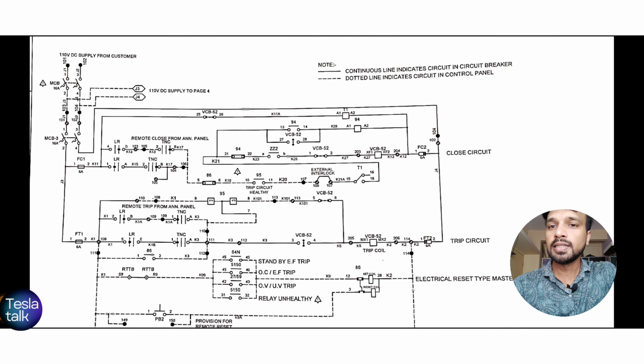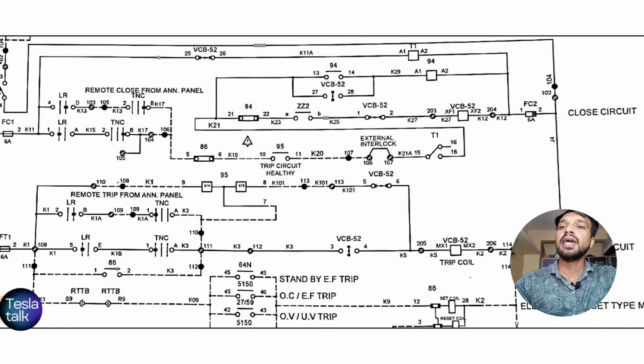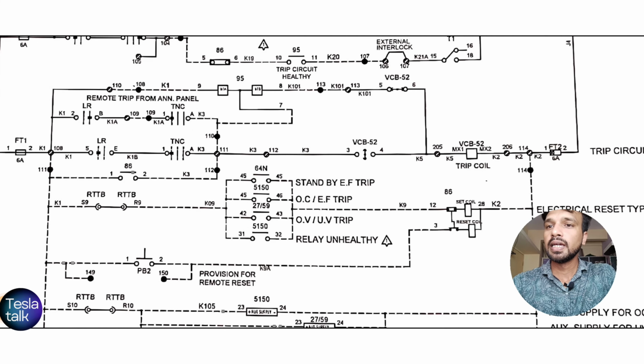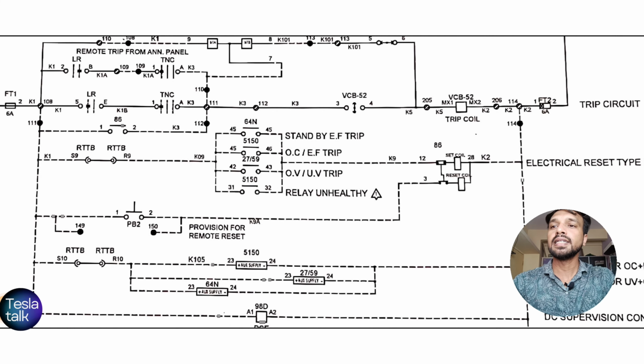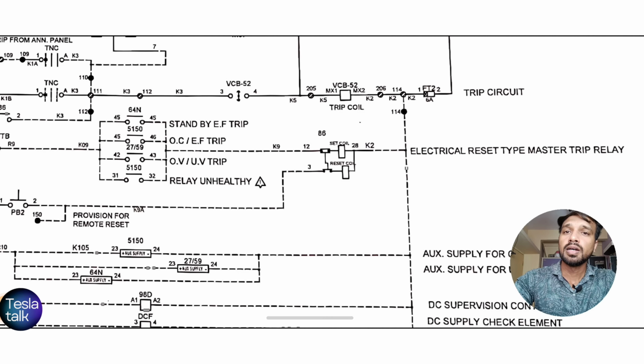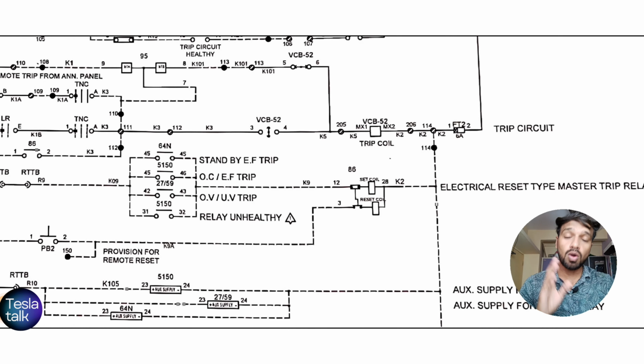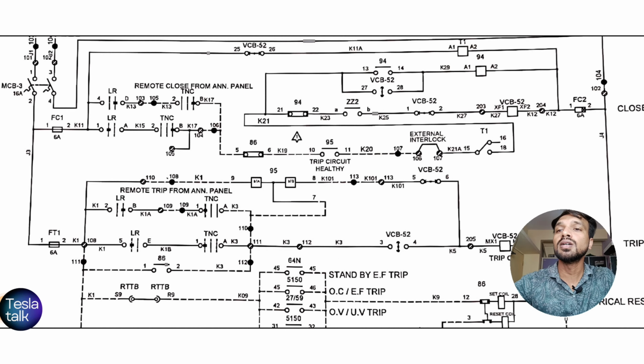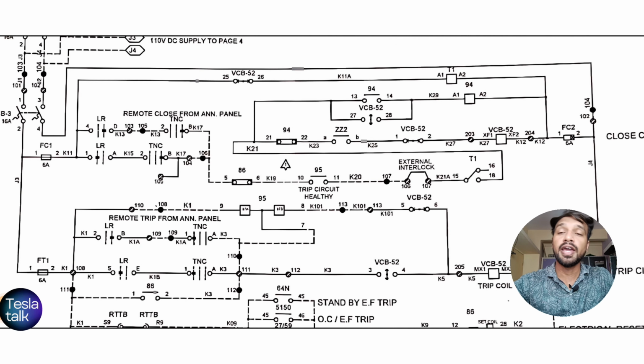So this is how it will work. If there is a fault, then this contact will get NC and the trip coil will get a supply. If there is any fault in the system, the relay will sense the overcurrent and send a command from this contact to the electrical reset type master relay, and the master trip relay will operate the trip coil and lock out the circuit breaker. So this is how the circuit breaker will trip by using the relay.